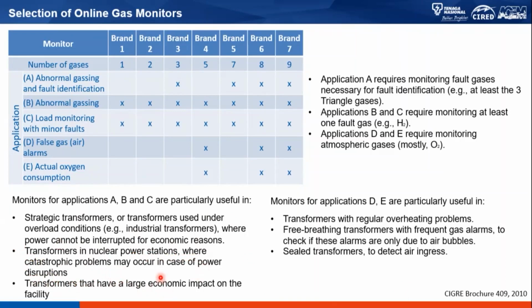There are more listed in the report, which you can refer to later. Monitors for applications D and E are useful for transformers with regular overheating problems, free-breathing transformers with frequent gas alarms, and for sealed transformers to detect air ingress into the transformer.